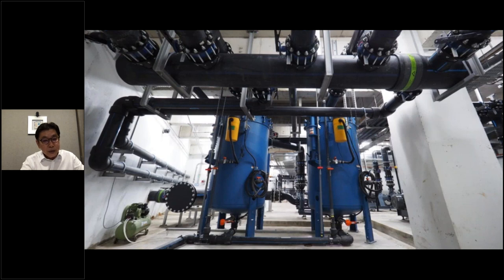8 years, no issue. Just imagine when you're using sand filters for commercial, I believe commercial usually takes about 2 years to change the media. On top of changing the media, like what Adam said, yes, it's a lot of problems. Really, I've been through taking out the media. It's quite tough. You've got to go into the filter, the other filter, to access and take out the media from the far end.